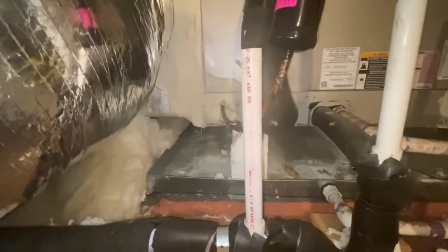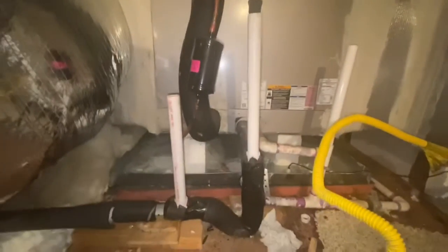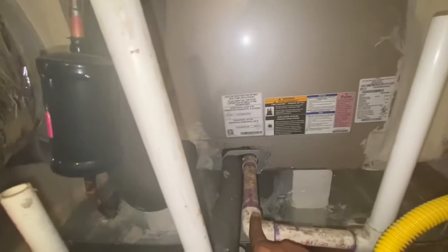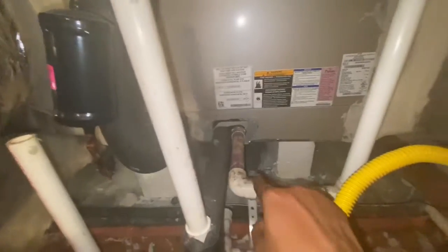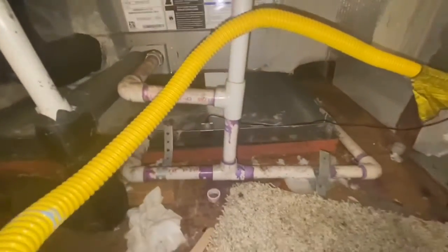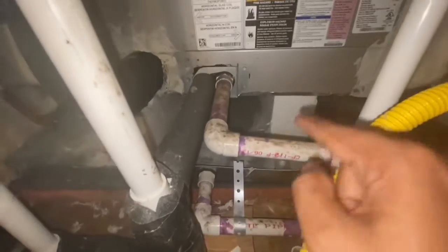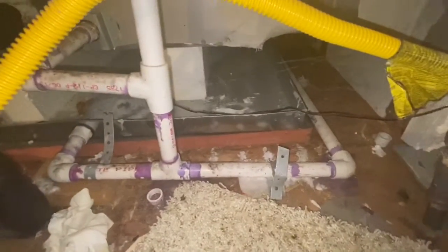In my case, when I came here, I really didn't see anything. There was nothing in the overflow pan, but the overflow line was still getting water flow. And when I came here, I had these three pipes, and I was confused about what is what and why the overflow occurs. What I figured out is that there are two lines coming from the unit, 1 and 2. The line on the right-hand side, in my case, is the overflow line, and it goes out somewhere. This is also connected to this pan, you see? So the overflow can happen in the pan as well as from the unit, and it gets collected and goes out through the overflow line.